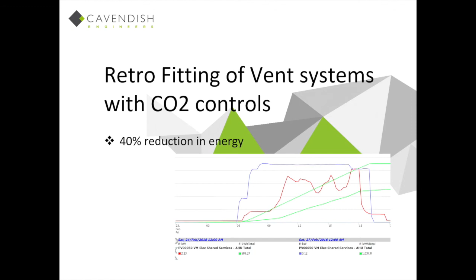You can see it doesn't actually start till 11 o'clock, because the CO2 hasn't built up. It goes off at lunchtime and then starts to build up again, just in response to the occupied load. You can see the 40% energy reduction in the fan there, just by intelligence.